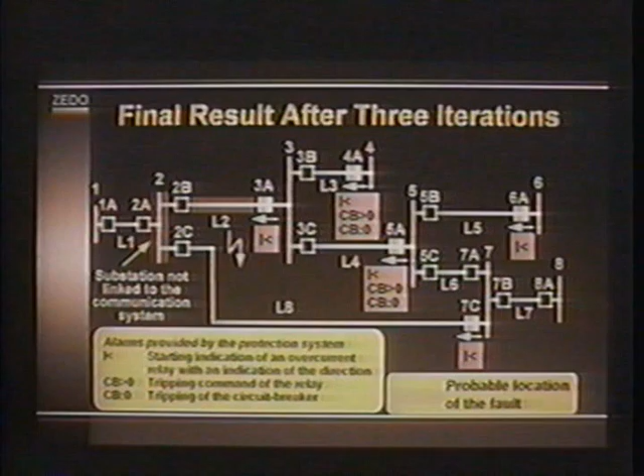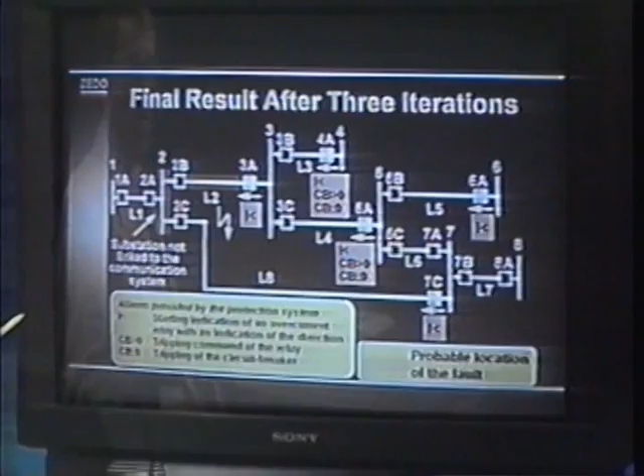So the final result after 3 iterations, meaning after 3 iterations the intermediate results do not change anymore, and that's the criterion for stopping the iterative process, is that only line L2, the real location of the fault, and the connected busbar are called a probable location of the fault. All other intermediate diagnoses regarding lines 3, 4, 5, 6, and 8 could be retracted, and this is the optimal interpretation of the information available in the control center.